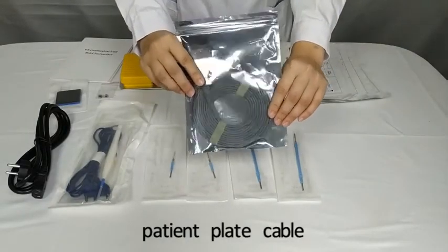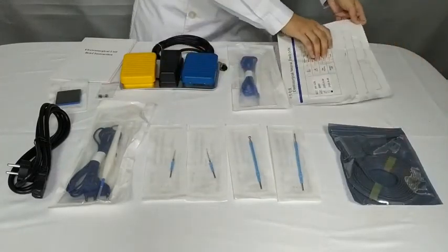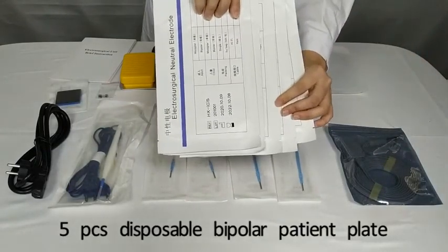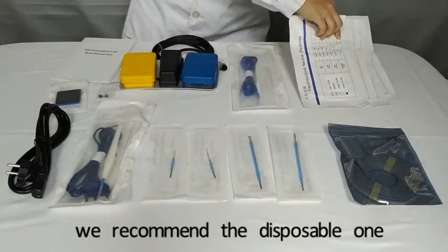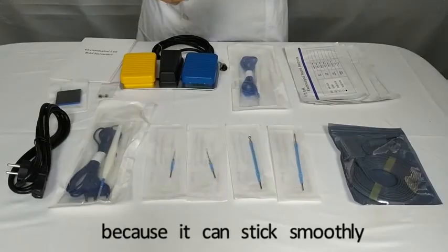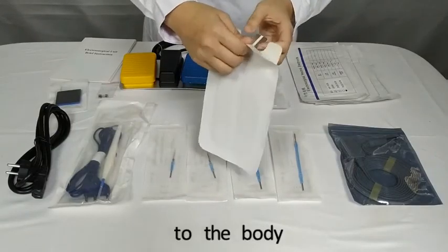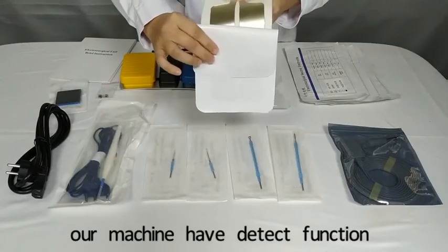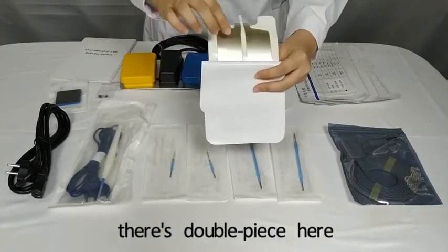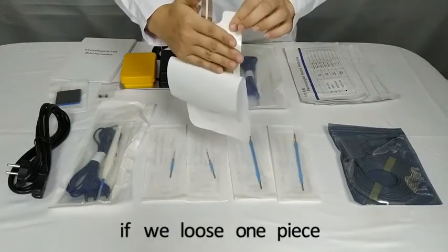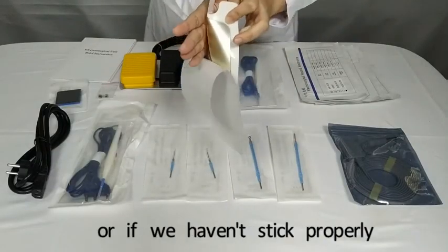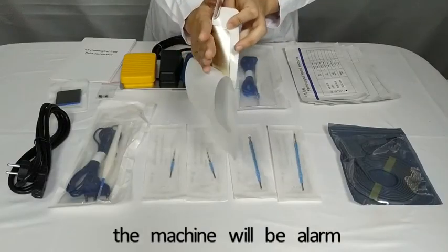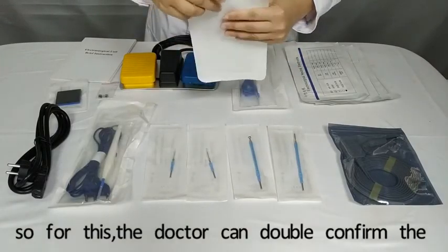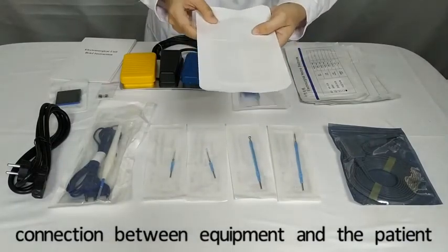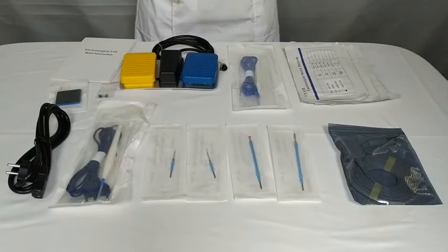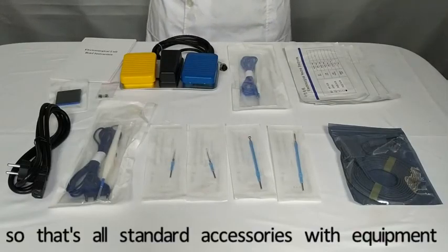Patient plate cable. 5 pieces of disposable bipolar patient plate. We recommend the disposable one because it can stick smoothly to the body. On the other hand, our machine has a detect function. There is a double piece here. If we lose one piece or if we haven't stuck it properly, the machine will alarm. So with this, the doctor can double confirm the connection between the equipment and the patient. So that's all the standard accessories with the equipment.